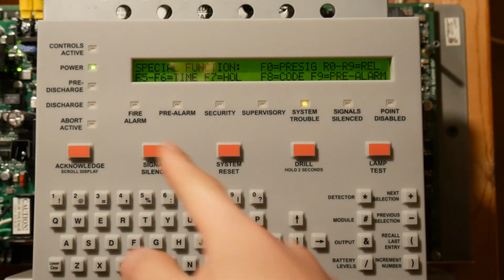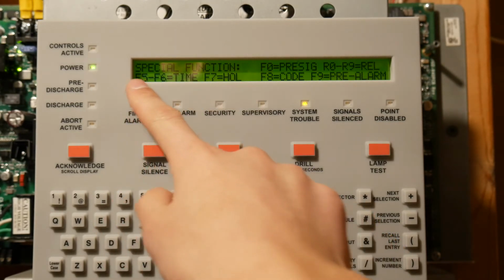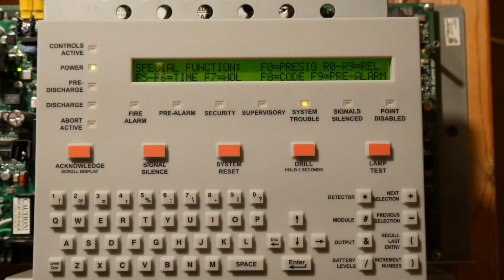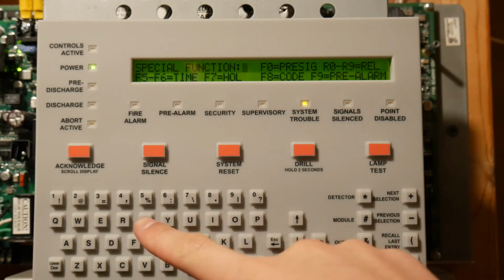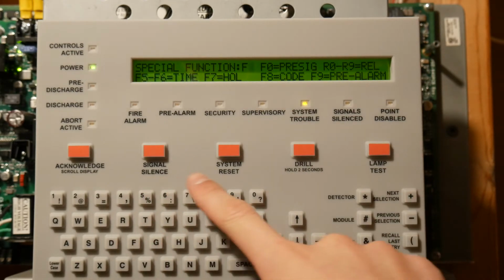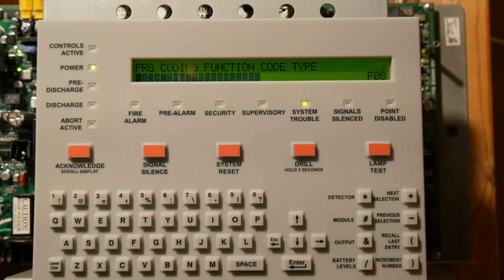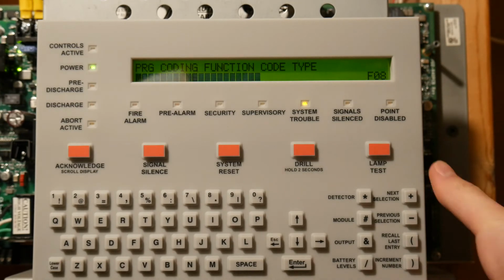So now we're going to go to F5, F6, and F7. I don't have to worry about those. That's basically for if you want to change the sensitivity of detectors and stuff like that. But now we're going to go to F8. F8 is your coding options for NACs. So if you have a NAC set as F8, it'll make the NAC what you have it set to.